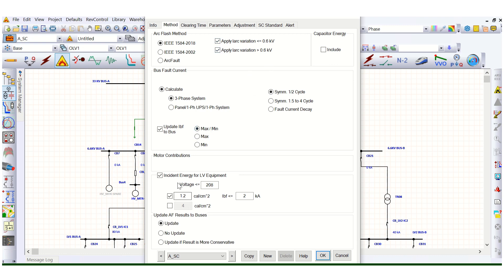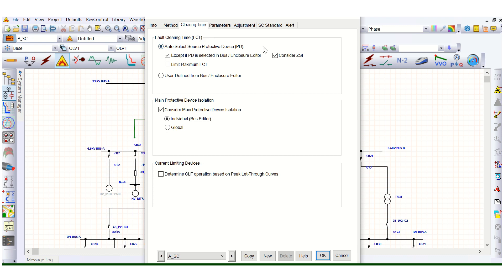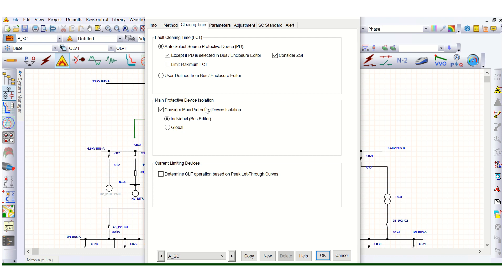Here, the incident energy for LV equipment is 1.2 calories per centimeter squared, and IBF is less than or equal to 2 kilo amps. The next step is the clearing time — your fault clearing time (FCT). The main protective device isolation can be set as individual or global, meaning, for example, a circuit breaker.